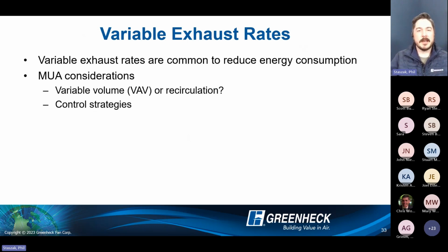Now, variable exhaust rates, I talked about the two different options and how we do this. It's very common, obviously, to reduce energy consumption. The more you can reduce airflow, the less outside air you're bringing in that you need to heat or cool, and then physically move with power, the horsepower of your fan. So variable volume or recirculation, that's your two options.